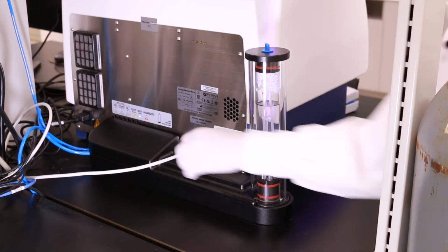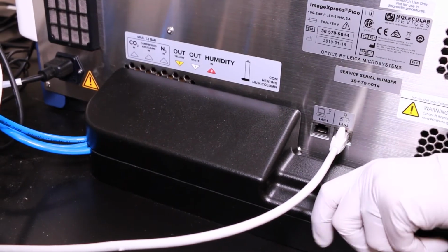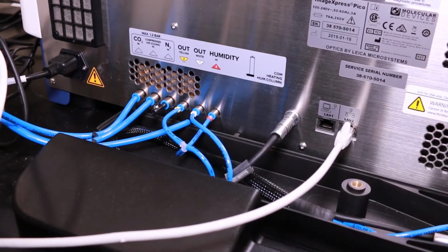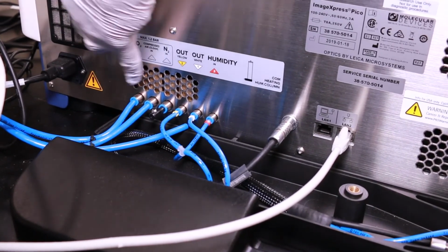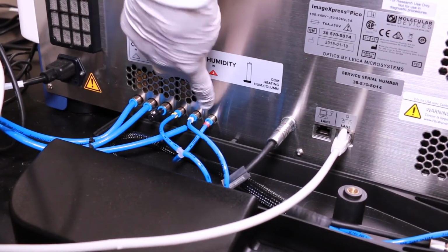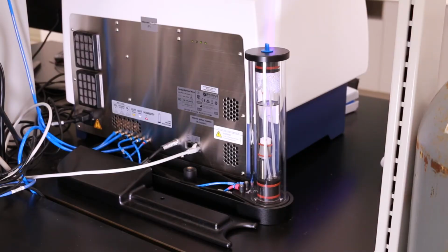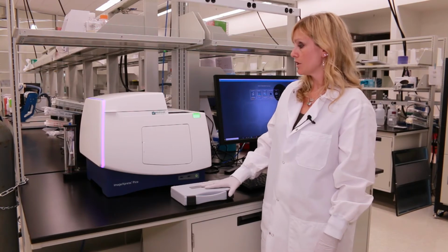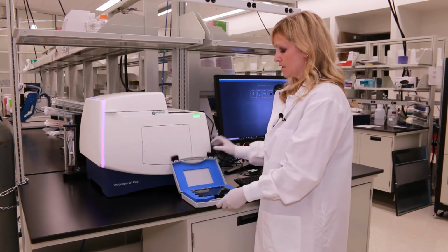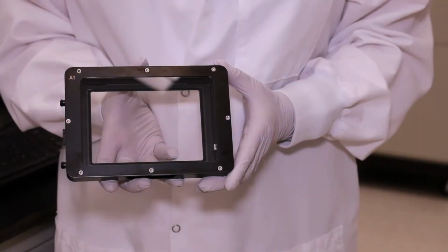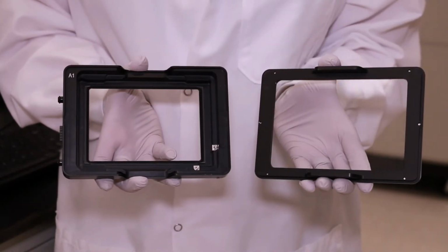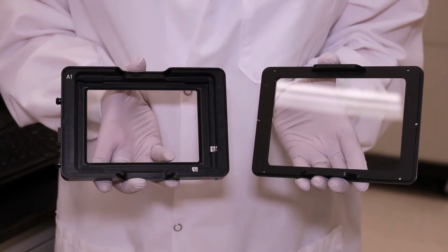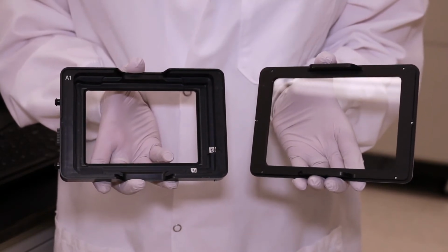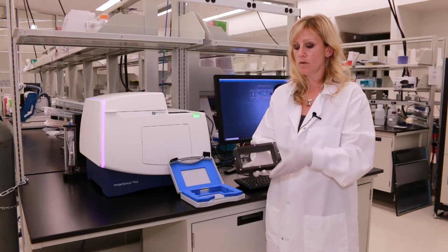In addition, on the back of the ImageXpress Pico, you've got these easy hookups to your existing gases. So you've got the CO2 inlet, the N2 inlet, and also the compressed air inlet that allows you to pump these gases in, and then on board the ImageXpress Pico is a gas mixer that mixes these gases and creates the perfect environment for your live cell experiments. When you're using the live cell imaging on the ImageXpress Pico, the nice thing about the design is that you're able to have a tightly controlled environment at the plate level. So in our environmental control cassette, this is where the mixed gases are pumped in, and you're able to have a tightly controlled environment right at the plate level.